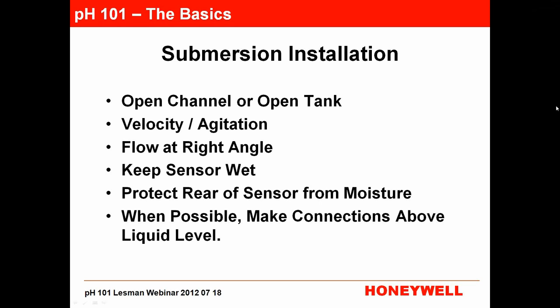Make your connections above the liquid level whenever possible. If you're using Honeywell's DuraFET, you need to make the connection right at the back of the sensor; if you're using a cable, you can make that connection higher. The reason is that lots of places have steam and condensate — I've seen sensors pulled out with a cup of condensate falling from the pipe. With the DuraFET 3, if you've made the connection correctly it should be good and tight with no moisture problems.